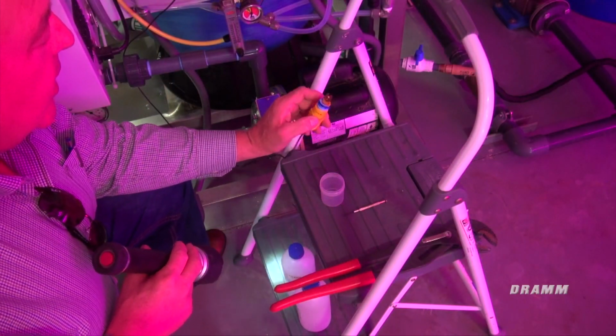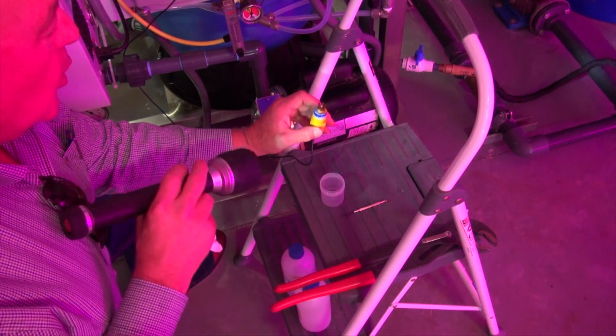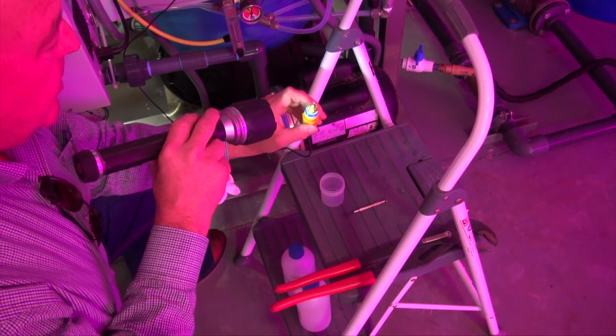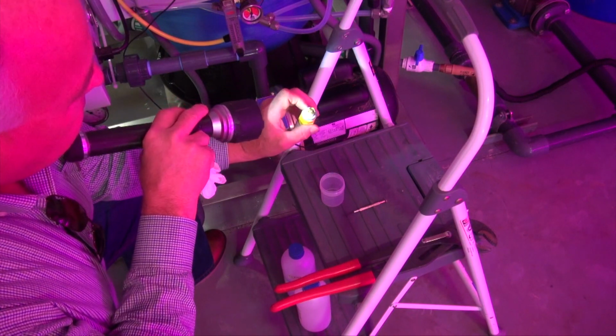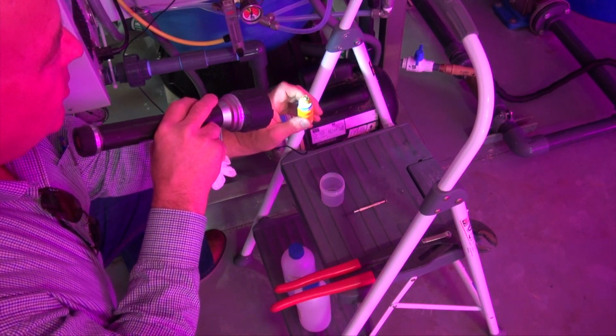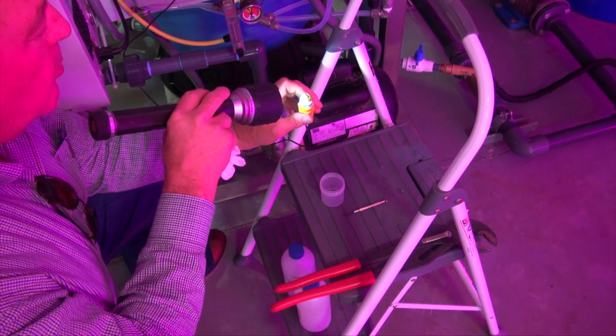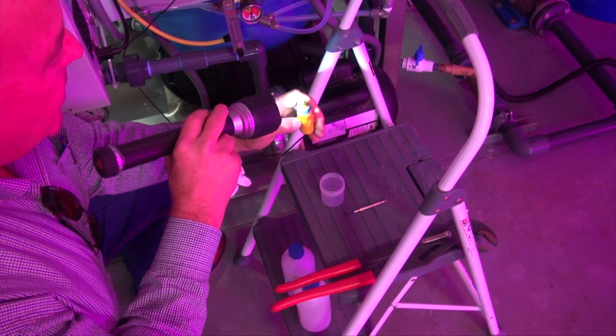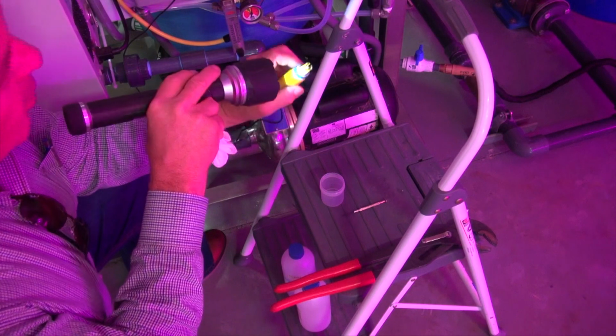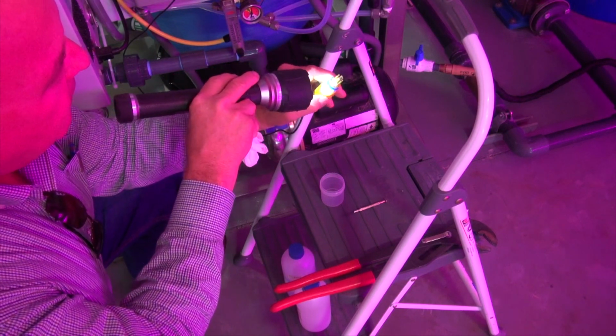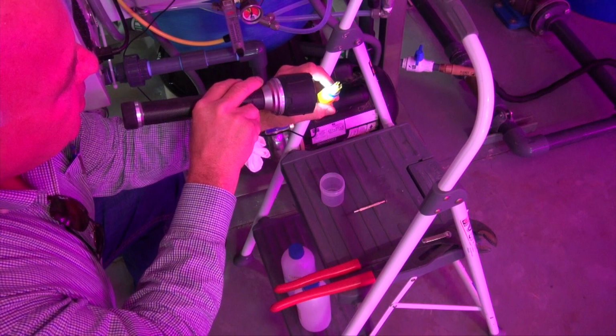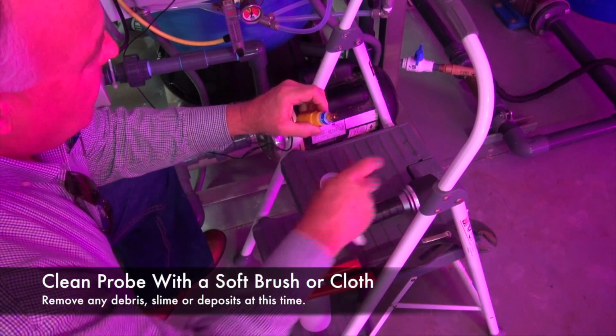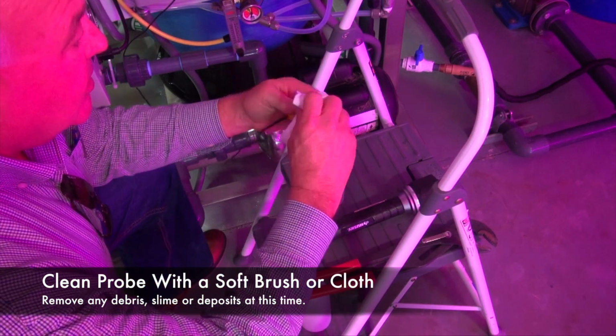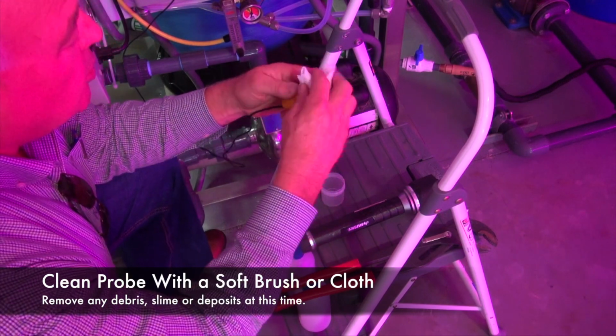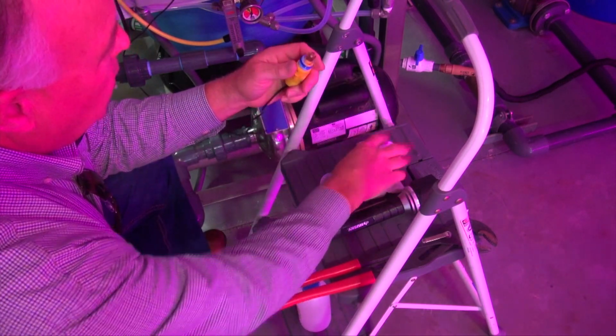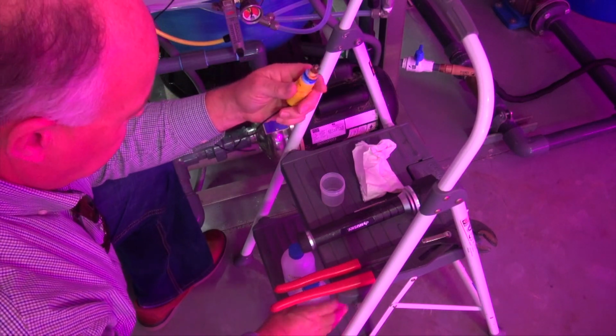All right, in order to calibrate the ORP sensor, the ORP probe, we first of all want to inspect it. So I'm just going to use a flashlight. It's a little dark here. Look for any particulate matter that's built up on the ORP probe tip. Algae buildup, any other deposits that have built up. Here we can see that there is a small amount of algae that's built up over time here, and so we want to wipe that off and clean it. For the sake of time, I'm going to just do a very cursory job of that right now so that we can get on with the calibration of the sensor.